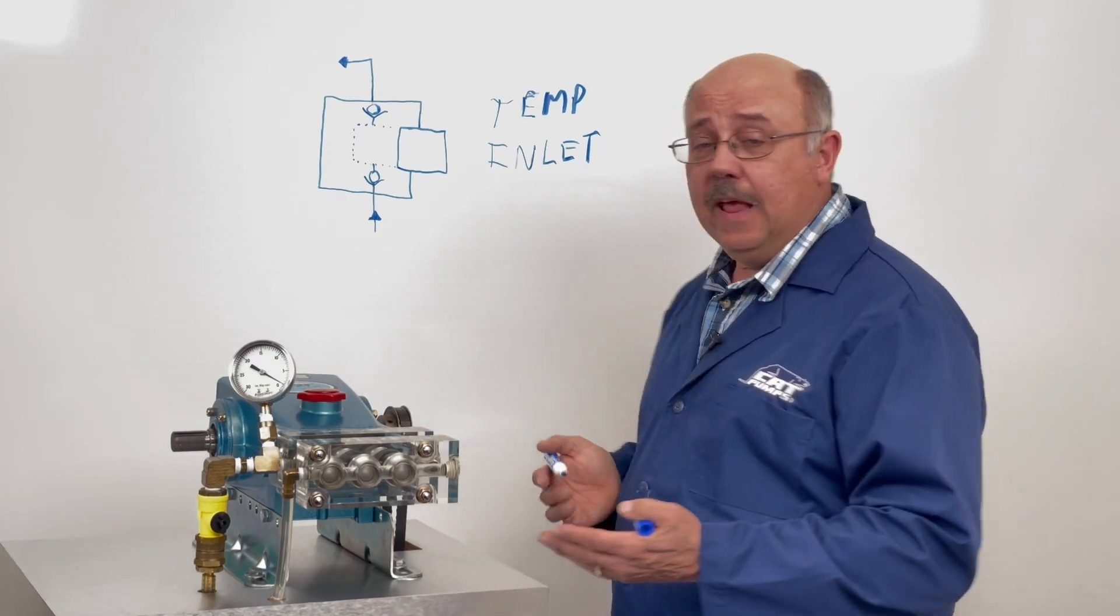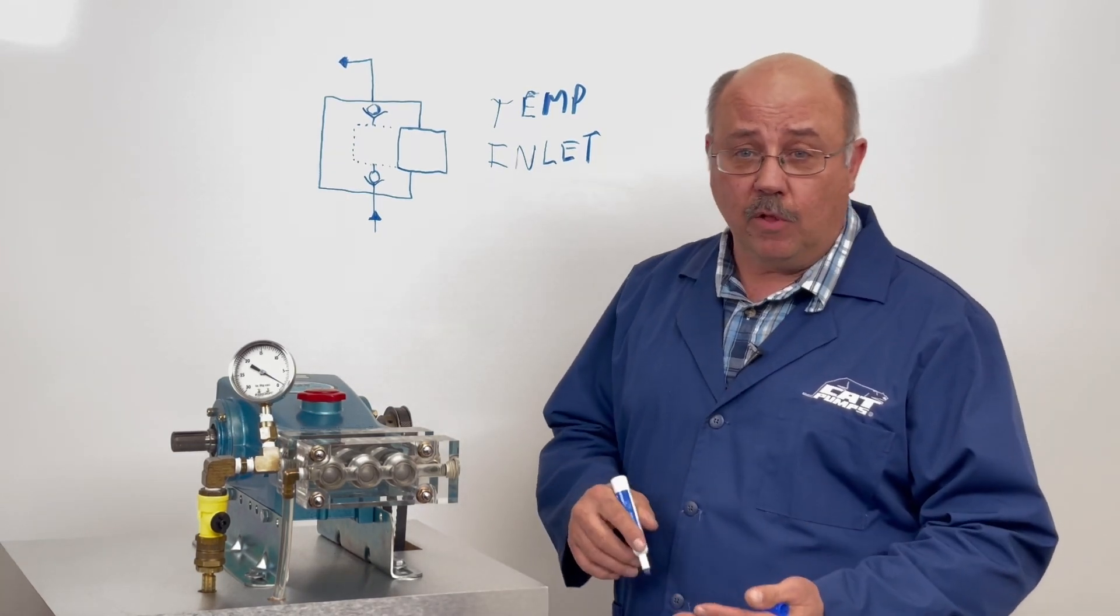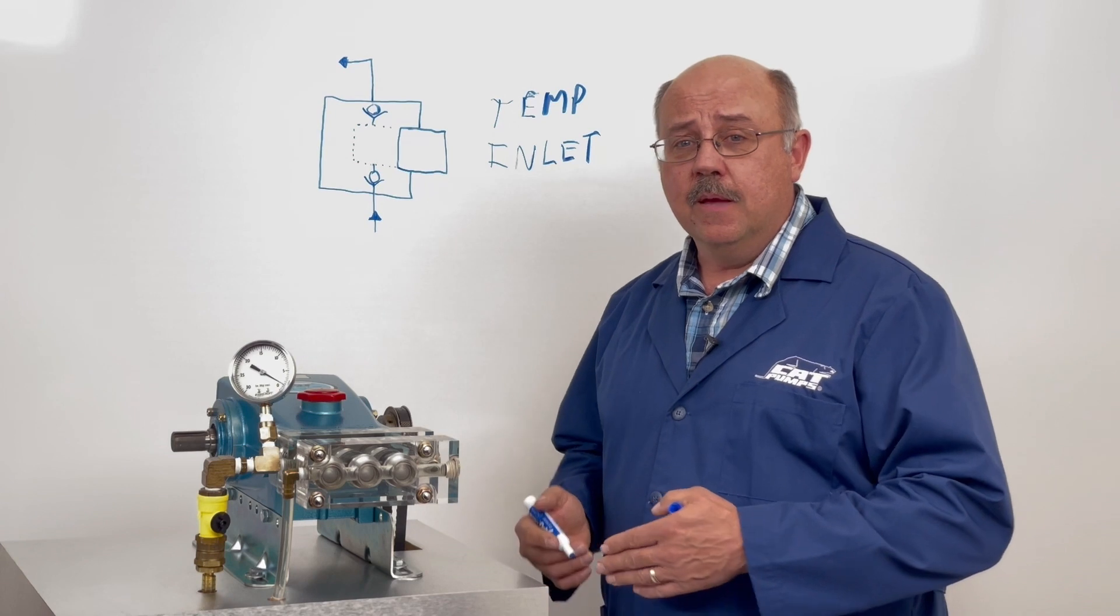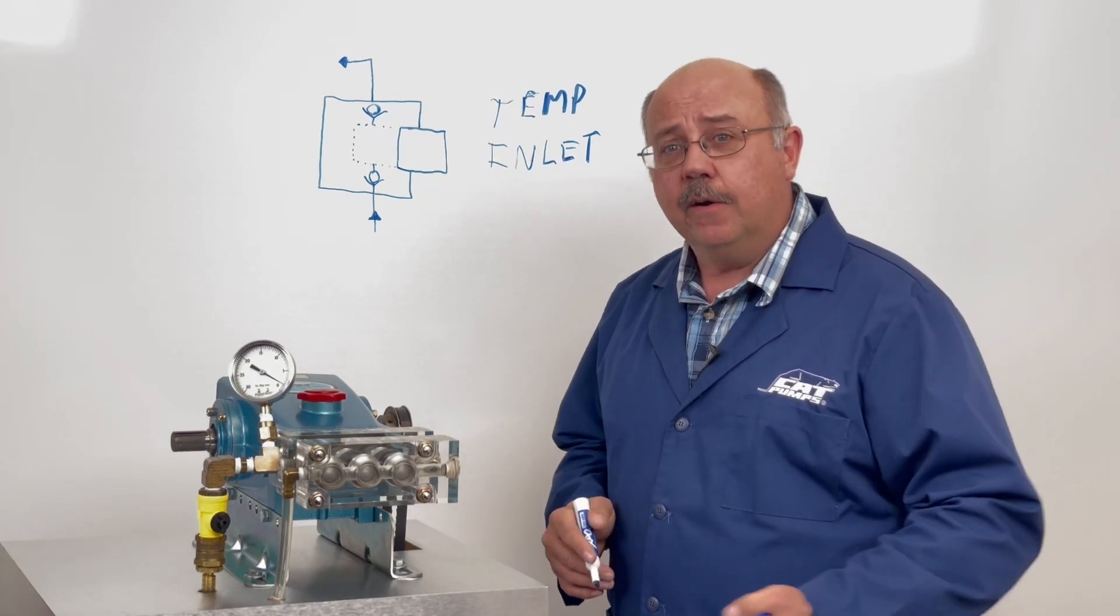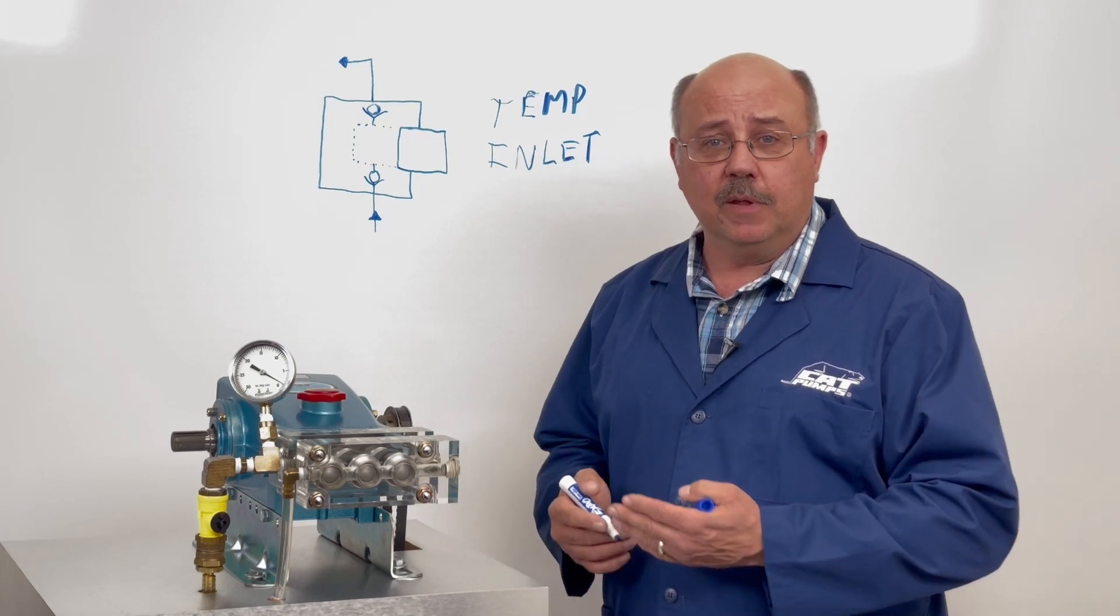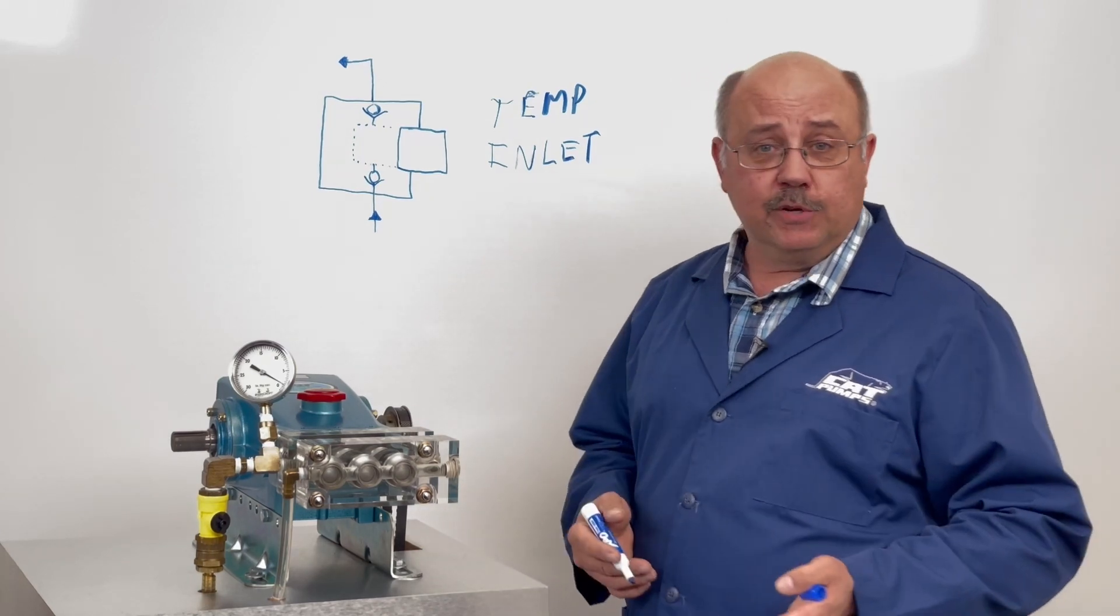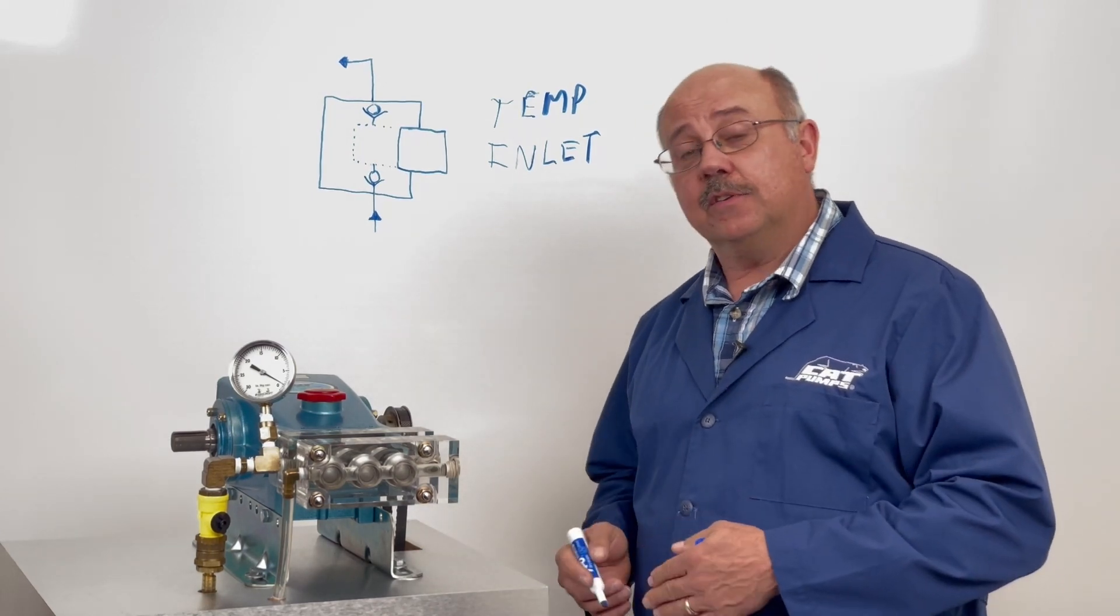The pumps are designed to handle their spec ratings as far as flow, pressure, RPM, but we still have to design a system so that we get enough water to the pump so that it can properly fill its chamber. The more restriction on the inlet, the higher the chances of cavitation.